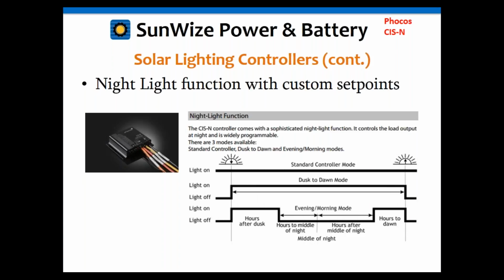This is another graphical representation of these light on, light off control structures that different manufacturers have slightly different takes on, but really it's very analogous in that you have an hours after dusk, potentially hours before dawn. One interesting feature that they have is a middle of the night feature, which is another set point that can be used to tweak the lighting a little bit more precisely. So now, rather than just basing your delays or your timers around dawn or dusk, you can now actually do that around the middle of the night.